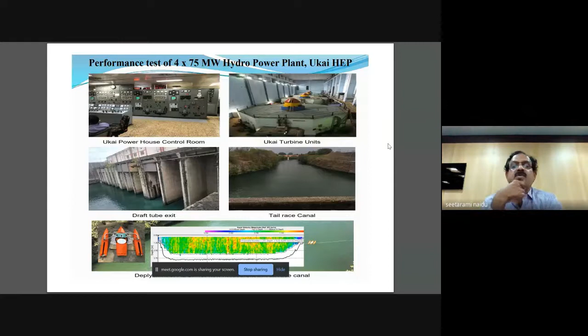Here, for the first time, CWPRS has used ultrasonic open channel flow measurement. Usually it is a well-known practice that flow is measured in closed conduit penstock, but away from that conventional method, we have proposed to use open channel measurement with this kind of ADCP. It is an American product, used to have a profile of water at the tail race, then integrate it for the entire area and measure the discharge.